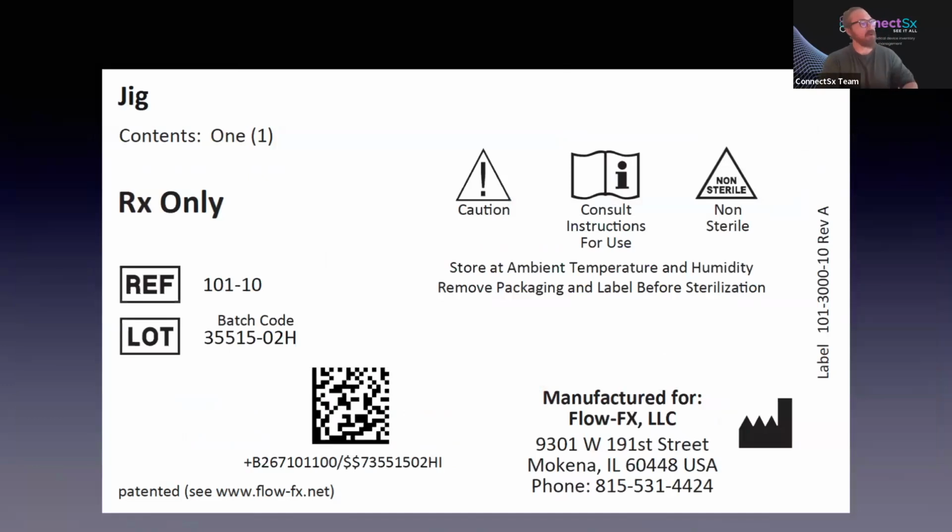So these are from a partner that we have, and I have 2 labels. This first one is pretty simple. There's not too much going on here. This is a reusable instrument. It is required to have a label, but it's not being sold. So this label has a little bit less impact maybe because that UDI isn't getting collected as often.